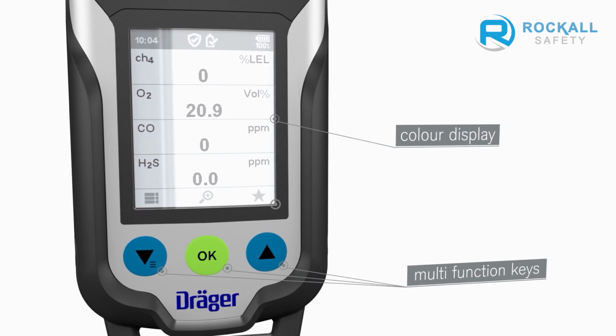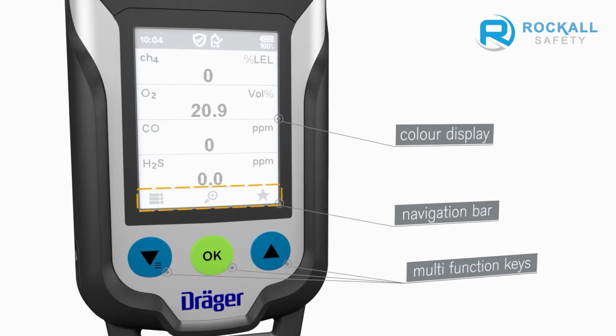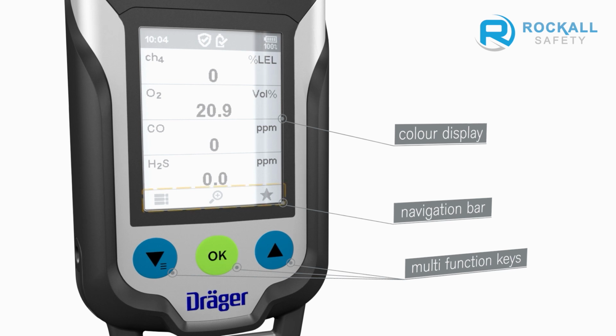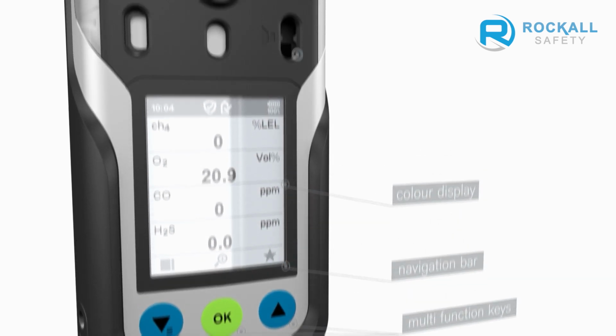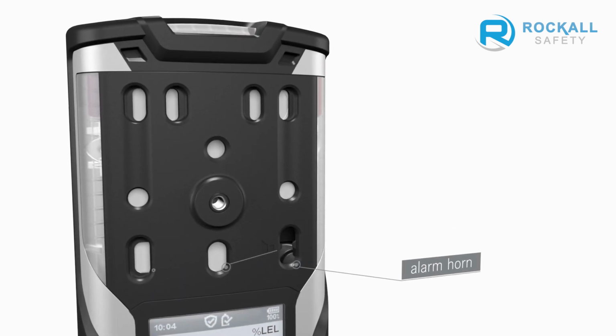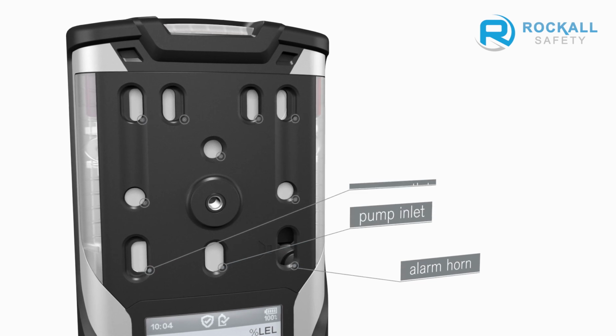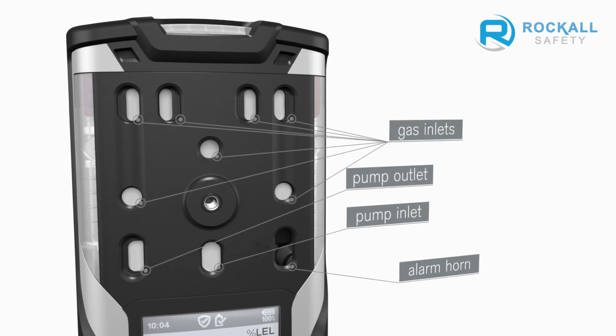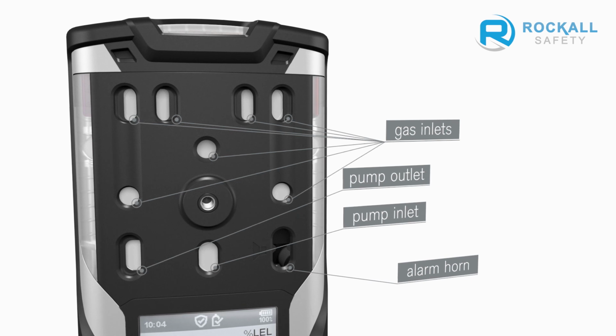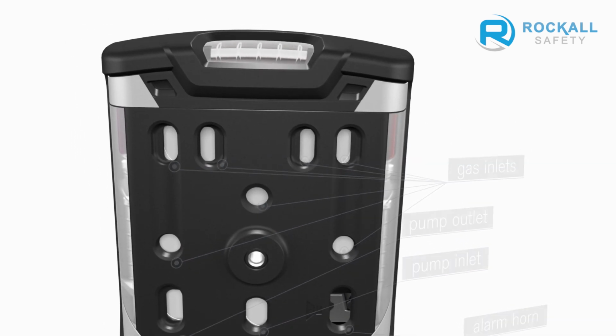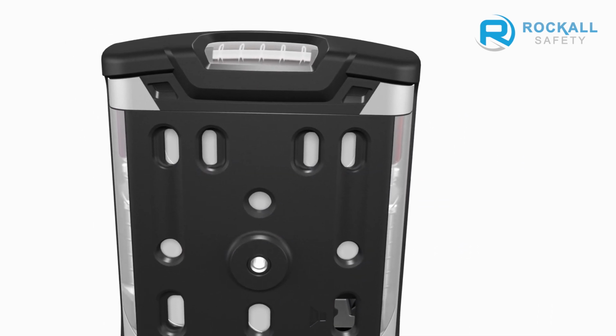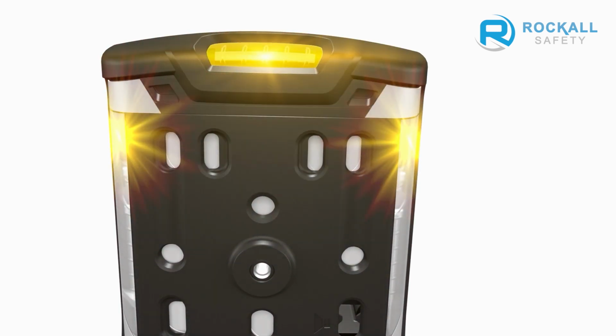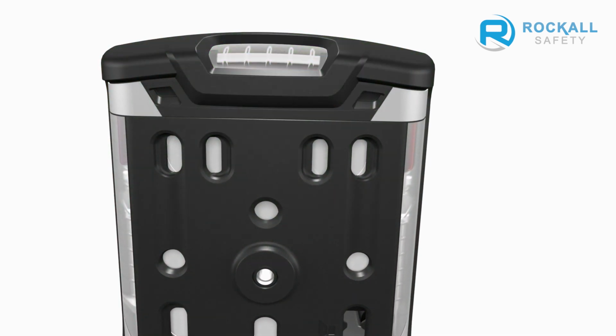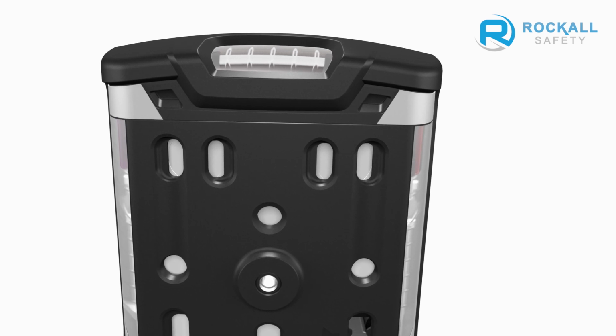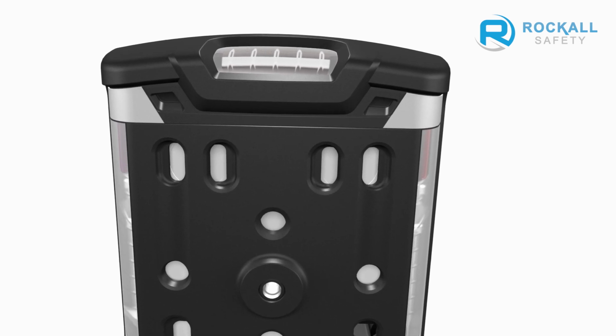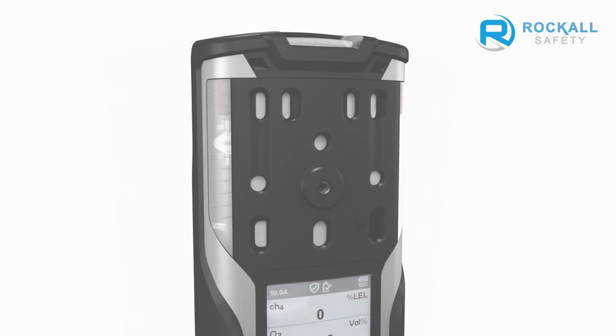During use, the keys perform various functions. These functions are indicated by the dynamic navigation bar in the display just above the keys. Located above the display are the horn, the pump inlet and outlet, and the gas inlets for the sensors. The top section of the Dräger X-am 8000 accommodates the readily visible LEDs, which illuminate red, yellow, or green, depending on the device's operating state. Additional information is provided in the Alarms chapter.